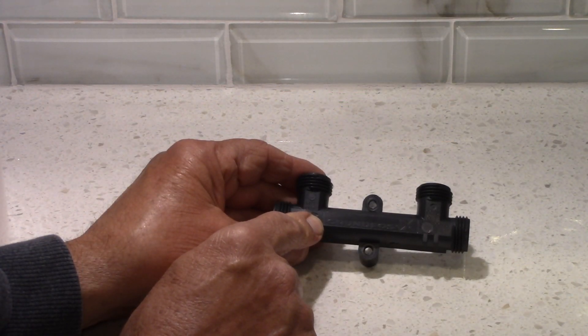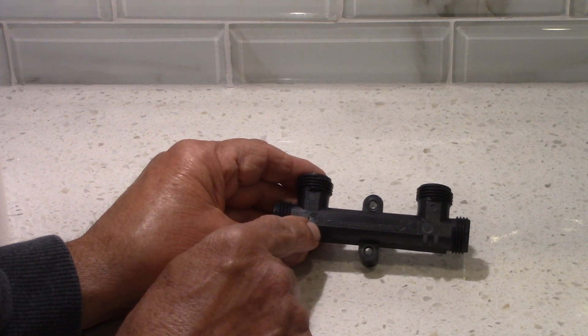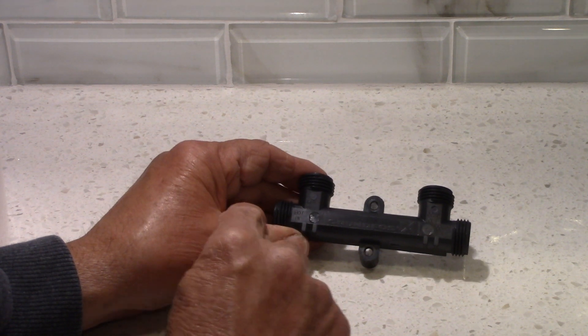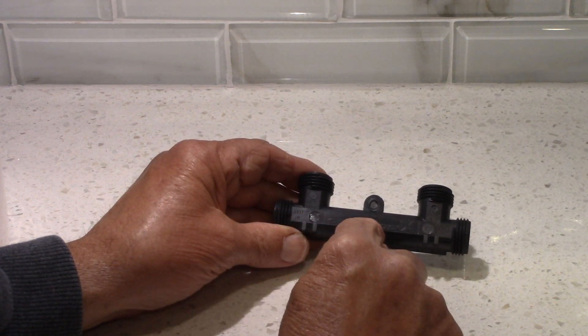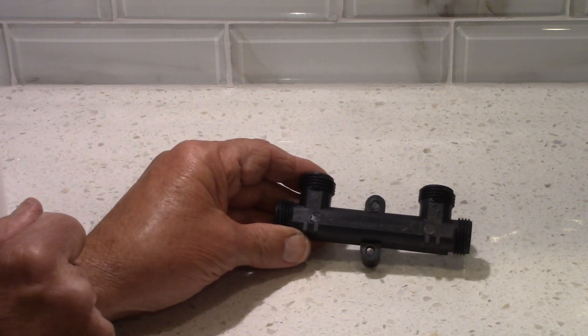I replaced the new one and very quickly after it was replaced, it started doing the same thing. Only this time it started letting the hot water bypass the shutoff valve and continue to circulate through the house, which is wasting energy.